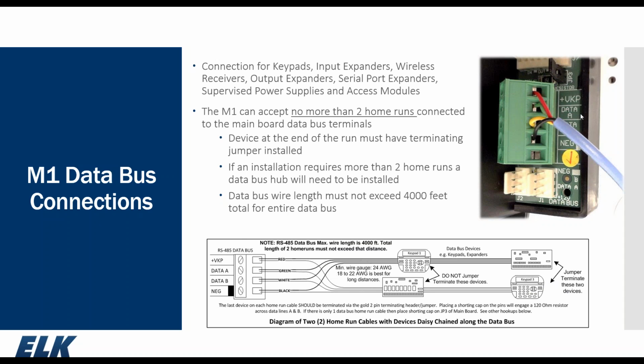Now, the purpose of the resistor is for balance of the bus, to help prevent any corrupt data from getting onto the bus. It's part of the 485 protocol for no more than 2 home runs, proper termination, and not to exceed a total of 4,000 feet when daisy chaining.